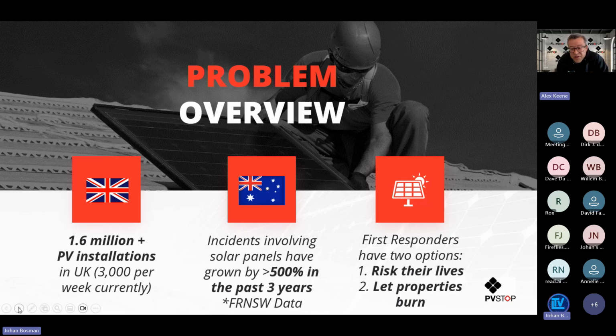The DC isolation switch is effective, but it's not particularly good at surviving in a rooftop environment exposed to the elements and water ingress. They found that 500% increase was a direct result of poor regulation in Australia, so there's a massive recall around that at the moment. But it certainly escalated everybody's awareness and understanding of these types of risks, and most importantly, first responders were the first to react and provide feedback on this.